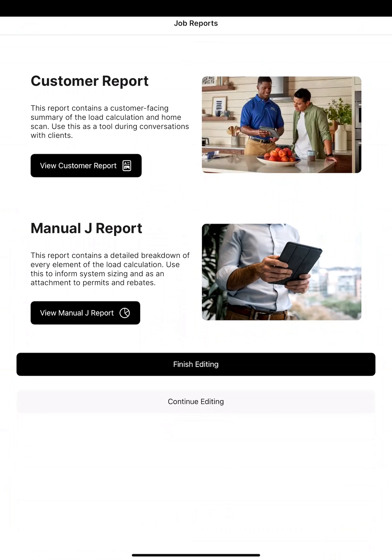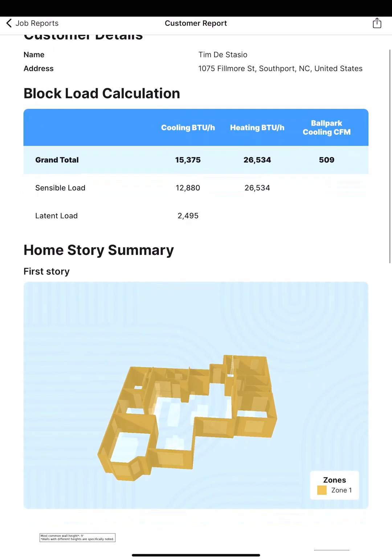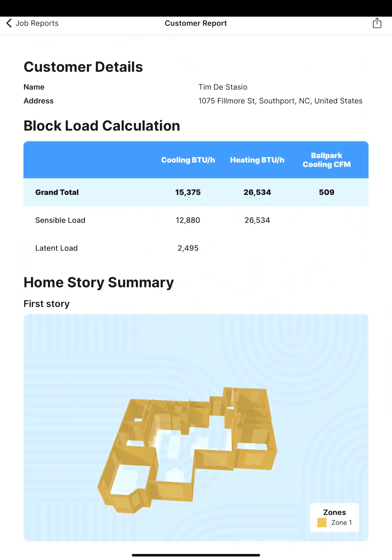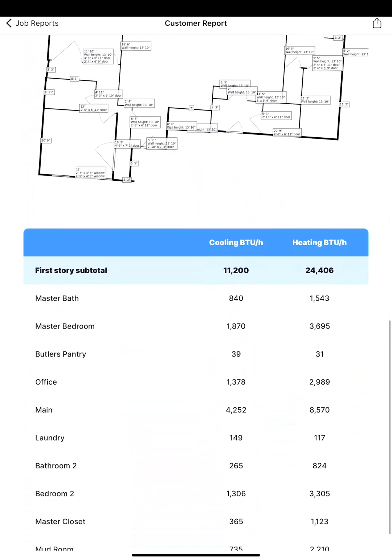We've got two different reports. One is a little more consumer friendly — it doesn't have all the contractor-level details, but you can see what the load is. From the extensive load calculations I've done on my house — I used Wrightsoft when I first designed it and even did a retroactive load calculation based on unit runtime — I can tell you I land right at 15,000 to 17,000 total cooling BTUs and 26,000 heating BTUs. You can trust these numbers. It even gives you your room-to-room heating and cooling BTUs, which is amazing. You can email the report to your customer or save it as a PDF.